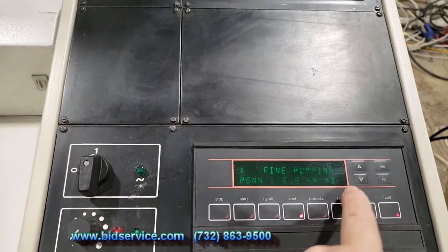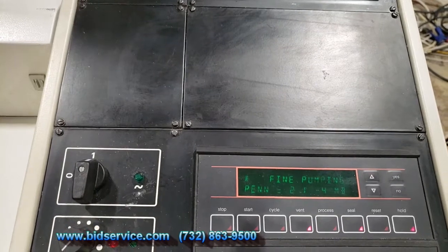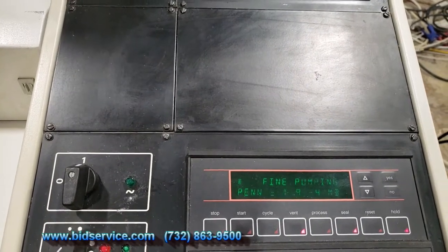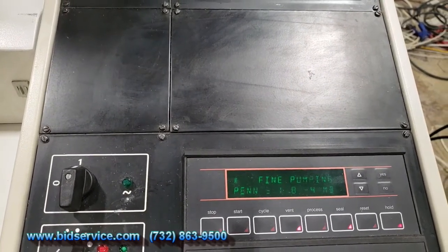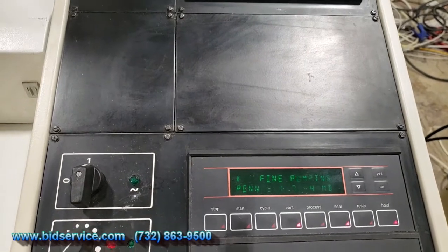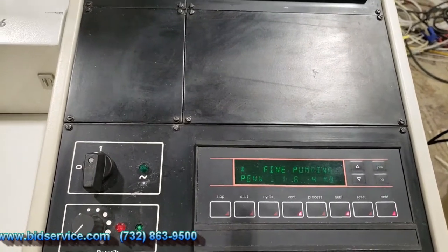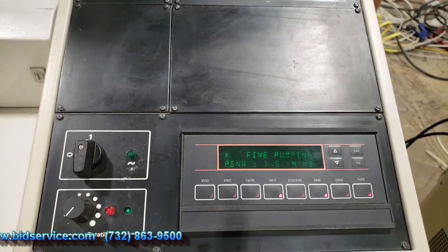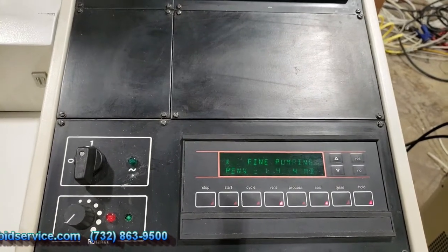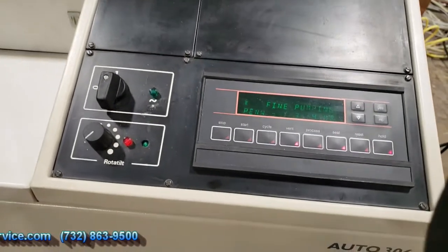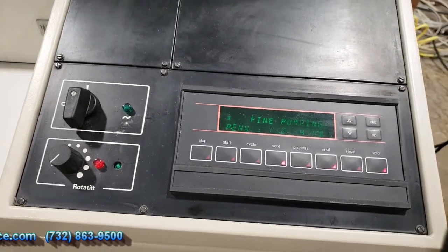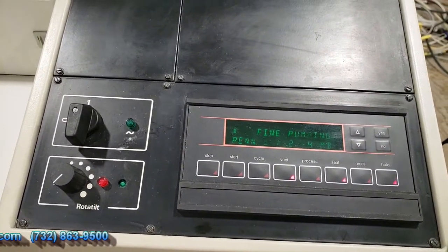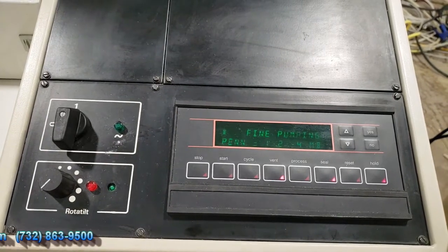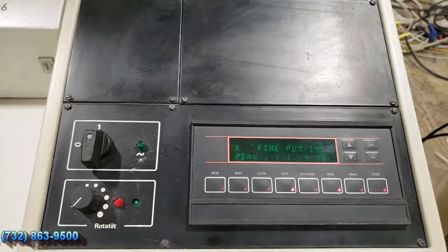And your penning gauge is going down. You can see it's 2 and a 4. And the system got down into 7 and a 7. That's without LN2. Usually you use your LN2 to help bring down the vacuum a little bit faster for your process, but this system works well enough that you really don't need the LN2. And that is the end of your test.